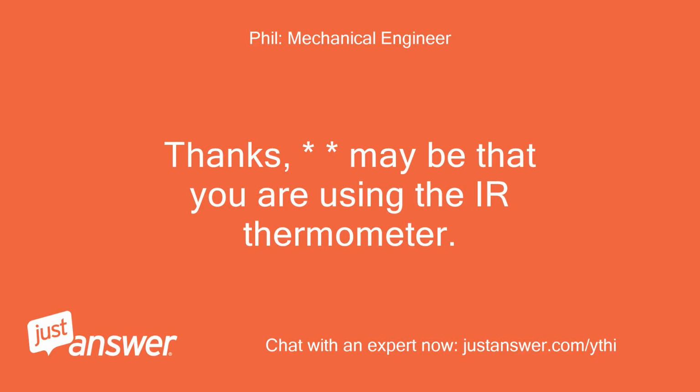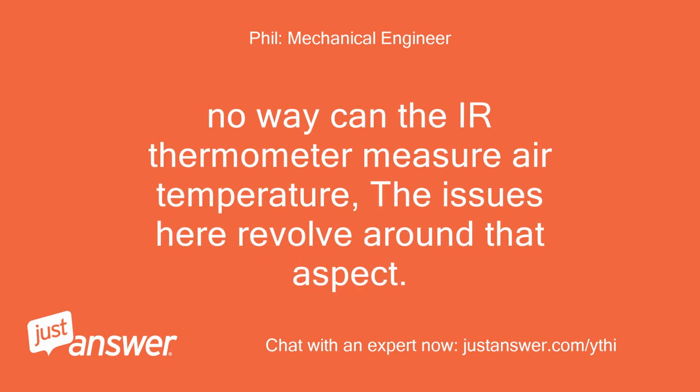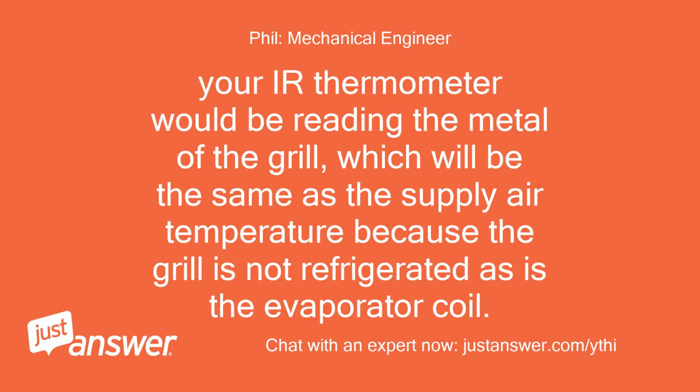Thanks. Maybe it is that you are using the IR thermometer. It only measures the temperature of objects, and the cooling coil or any surface on it in this case will always be colder than the air temperature. No way can the IR thermometer measure air temperature. The issues here revolve around that aspect. Your 55-57°F reading earlier is the supply air grill temperature. Your IR thermometer would be reading the metal of the grill, which will be the same as the supply air temperature because the grill is not refrigerated as is the evaporator coil.